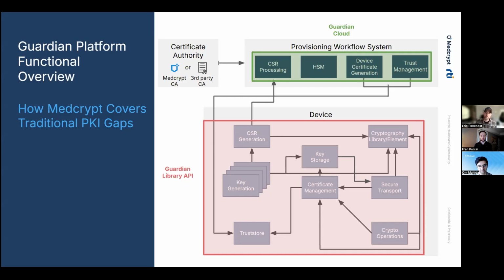Before we dig into the individual pieces, an important thread that we'll see in this demonstration is the establishment of trust among the components of the medical device. Even with cryptography turned on, with a library like OpenSSL, and data being encrypted, signed, and authenticated cryptographically, it doesn't mean the device is actually operating securely. We'll see that in a little bit here. Proper trust is required to enable security that satisfies the FDA cybersecurity guidance for medical devices.